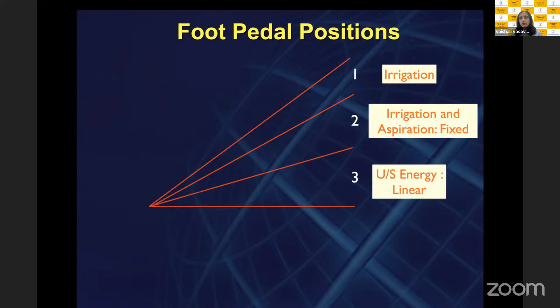So again, in this foot position 3, which is where all the energy is being given. Now it depends, the foot, you only have a fixed amount of travel that you will have in any foot position. Now it depends on how much energy you set. Like on the left side, if you see, I have preset an energy of 50%. So from 0 to the end, it will only go to 50%. So it's a slow increase if I put it on a linear mode.